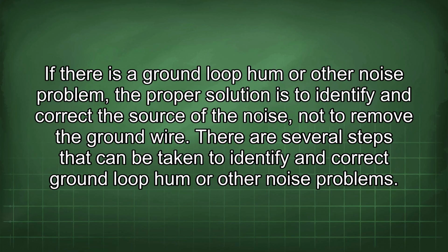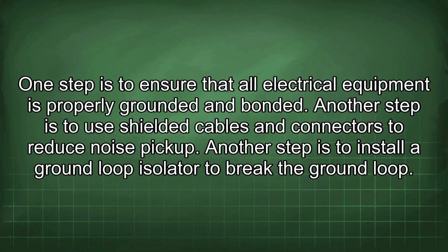If there is a ground loop hum or other noise problem, the proper solution is to identify and correct the source of the noise, not to remove the ground wire. There are several steps that can be taken to identify and correct ground loop hum or other noise problems. One step is to ensure that all electrical equipment is properly grounded and bonded. Another step is to use shielded cables and connectors to reduce noise pickup. Another step is to install a ground loop isolator to break the ground loop.